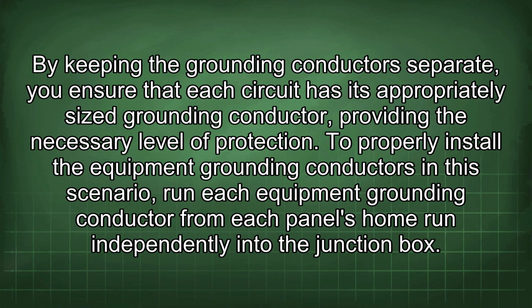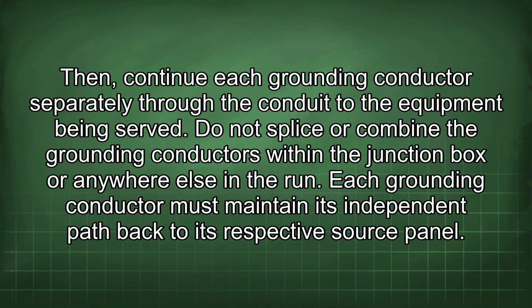To properly install the equipment grounding conductors in this scenario, run each equipment grounding conductor from each panel's home run independently into the junction box. Then continue each grounding conductor separately through the conduit to the equipment being served. Do not splice or combine the grounding conductors within the junction box or anywhere else in the run. Each grounding conductor must maintain its independent path back to its respective source panel.